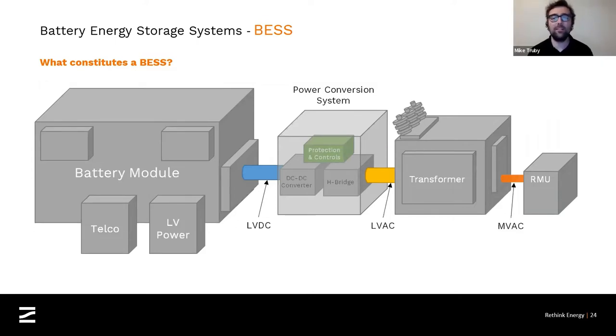And what it will typically include is some kind of filtering circuit. What you can see on the left here is actually perhaps a little unusual. A DC to DC converter would normally only be used in an application where you have a variable DC voltage. So maybe where you DC couple the solar park to your battery at the DC level. It may be normally more of a simple system, but that will then pass through into some kind of switching circuit, which is shown here. An H-bridge, again, a relatively simple switching circuit. And what this will do is it will use power electronics and some kind of methodology like pulse width modulation or space vector modulation to transform that DC current into an AC current.